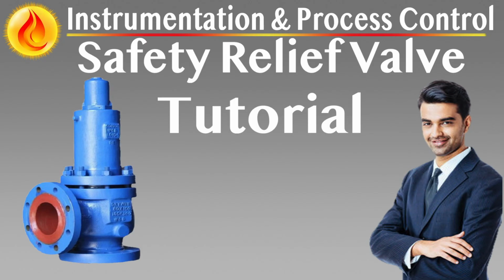Service-specific restrictions. Balanced bellows valves should not be used in reciprocating compressor discharges. Vibrations and pressure pulsations can cause fatigue cracking in bellows. In coking or fouling services, accumulation within the bellows chamber can lead to mechanical blockage, compromising movement.